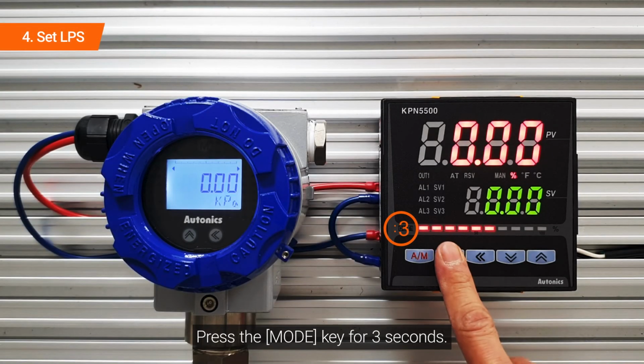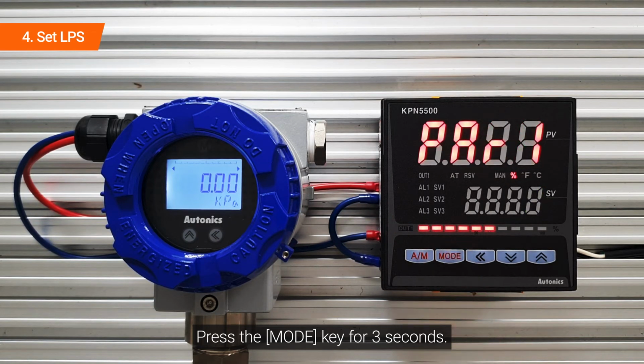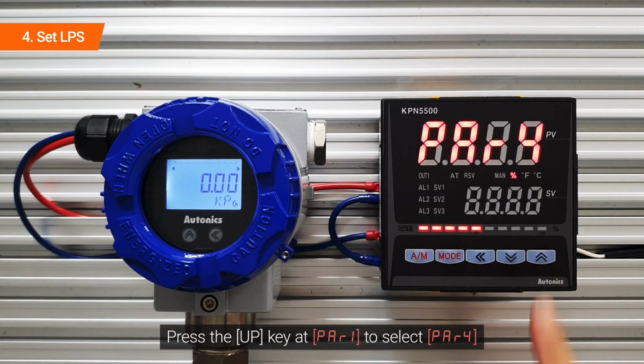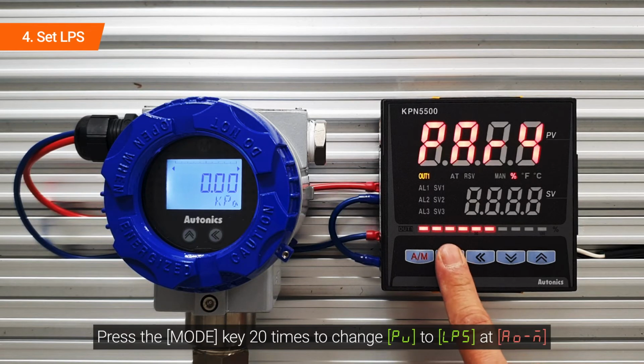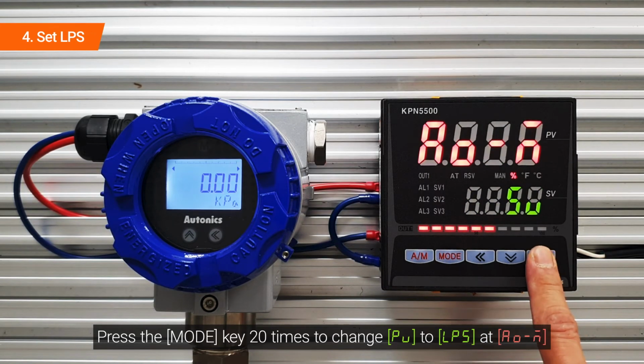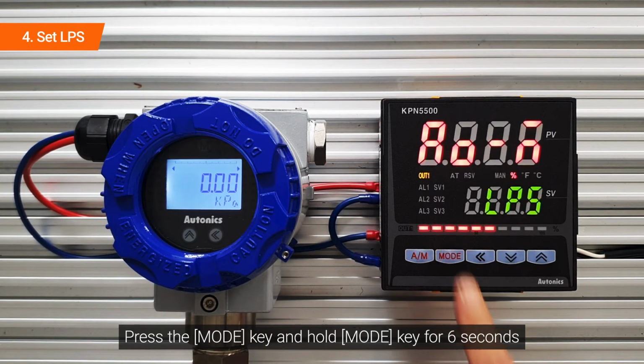Press the mode key for 3 seconds. Press the up key at PAR1 to select PAR4. Press the mode key 20 times to change PV to LPS at AO-M. Press the mode key and hold mode key for 6 seconds.